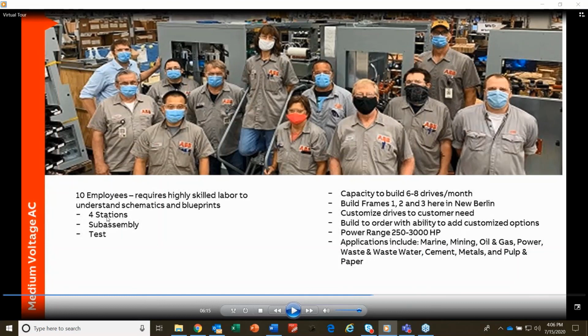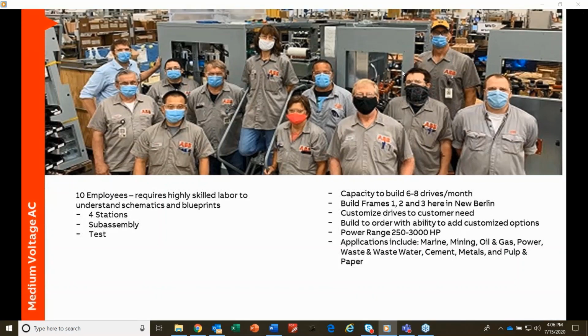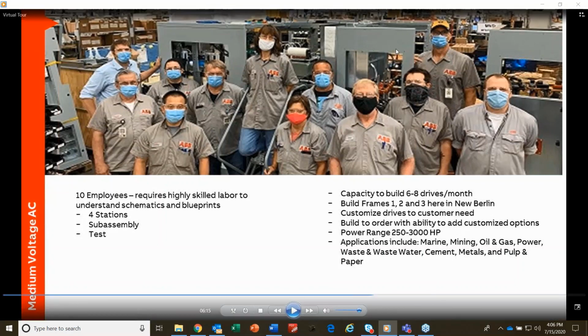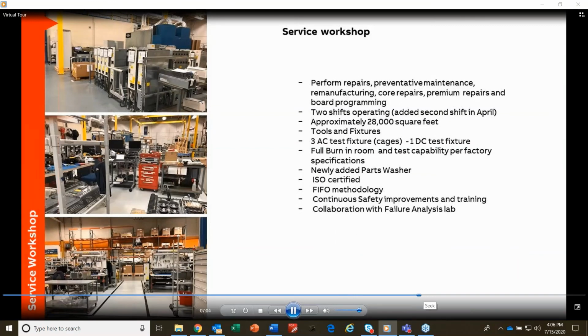These are a lot more labor intensive, and this is the team that builds these. There are 10 employees, working through 4 stations doing sub-assembly and test. We test each and every drive at the factory. They build these in New Berlin, medium voltage, 4,000 volts, built to order, and they're very customizable to a degree. We only make the drive, not the electronic controls, and typically partner with other ABB divisions to provide the circuit breakers, disconnects, and other equipment we typically produce with these units.